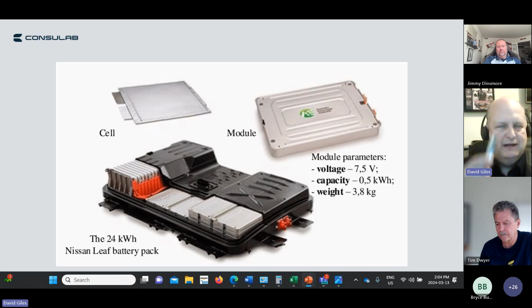So they don't release a lot of information, but we do know that battery cells that reach around 55 to 60 degrees Fahrenheit above normal can cause the battery to go into a thermal event. So the battery cells themselves are actually protected. Inside, the first plate, as the battery starts to get warm, actually pushes up on a disc inside the cell, which allows expansion to happen within that cell, hoping that the thermal management system can actually cool that cell down.